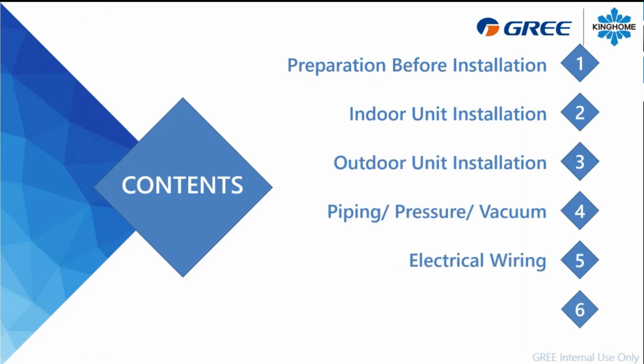So today we're gonna see how to be prepared for your installation. We're gonna walk through the indoor unit and the outdoor unit as well. We're gonna take a small review about the piping, pressure, vacuum, all the stuff you need to do to be done perfectly when you want to do a good installation. We're gonna see the electrical wiring, and at the end of the presentation, there will be a test and run: how to control and make the startup for the unit, how to program everything via the dip switches, and how to make it work correctly.